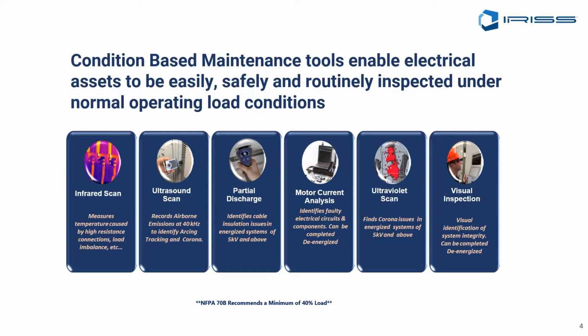Partial discharge testing is specifically looking for discharges that are happening inside the insulating material of medium and high voltage equipment. Motor current analysis, again, we can hook up to our motors and diagnose when we're seeing unusual current and voltage activity in the power signature that the motor is drawing. Ultraviolet scans can pick up corona. It's a camera that looks at light above the visible range. And then, of course, visual inspection, as I mentioned before.